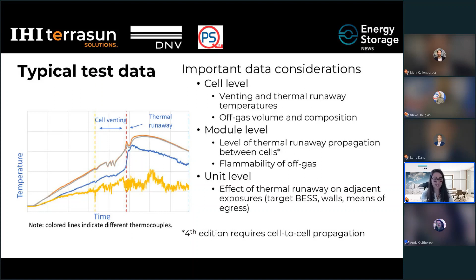And then the flammability of that off gas is also important for the module level. And the unit level, the effect of thermal runaway on the adjacent exposures, and the exposures are defined as that of the target BESS surrounding the initial unit, the walls, any walls that are present, and then the means of egress.